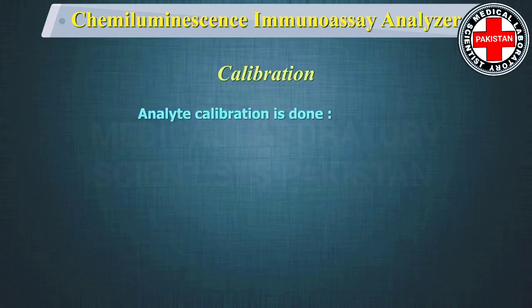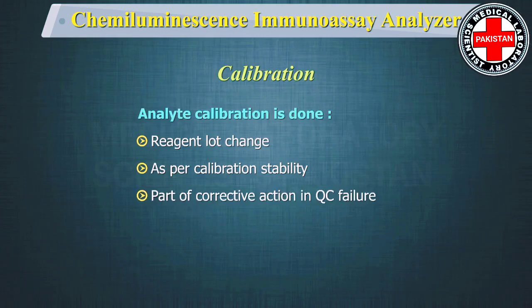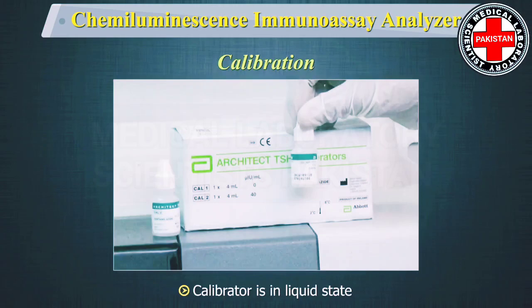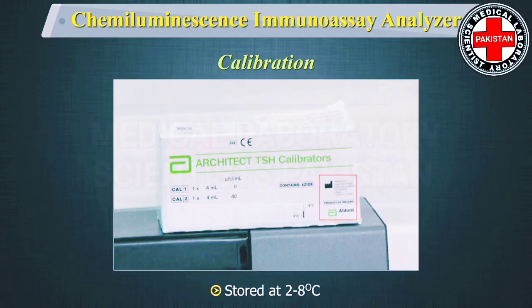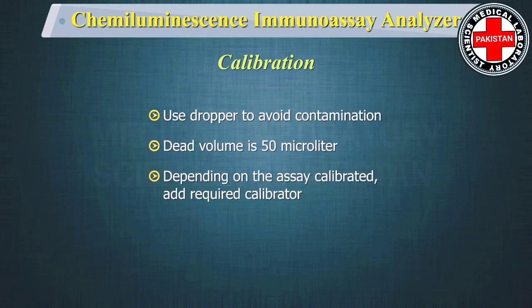Analyte calibration should be done when there is a reagent lot change, as per the calibration stability, or as part of corrective action in quality control failure. In this system, the calibrator is in liquid state, stable until expiry after opening, and stored at 2 to 8 degrees centigrade. Use the dropper provided to avoid contamination. The dead volume is 50 µL; therefore, depending on the assay calibrated, add the calibrator volume required.